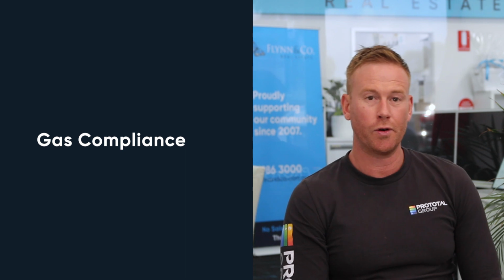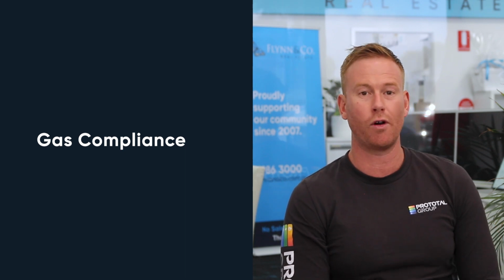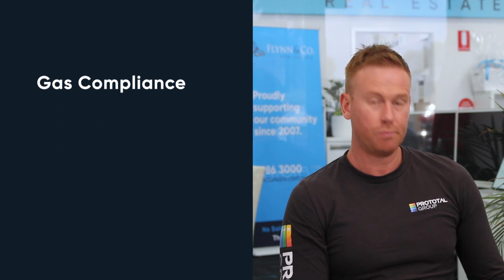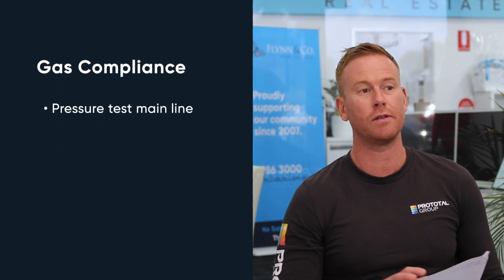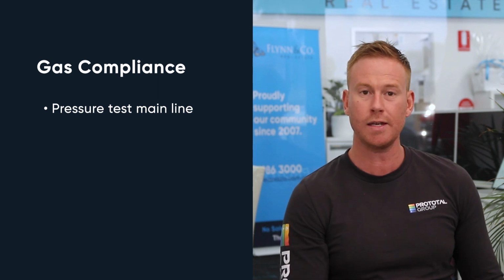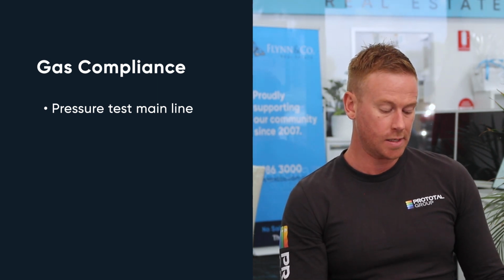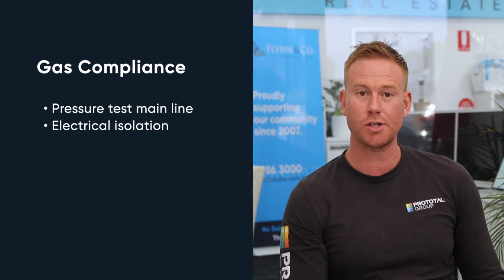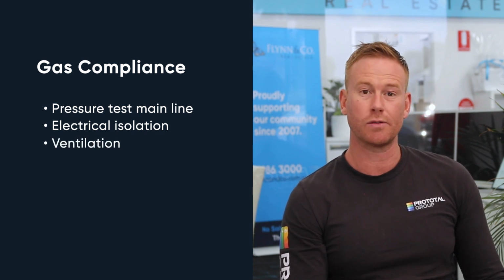Our gas safety compliance inspection caters for all testing in accordance with AS 5601 and includes pressure testing the main line, so testing your whole installation of pipework for leaks. There's a number of tests we need to do, checking electrical isolation points. Ventilation is a really important one within heating. We check the integrity of flue cowls. We also conduct negative pressure tests if required, check connections of appliances for leaks, and complete combustion, so flue gas analysis.